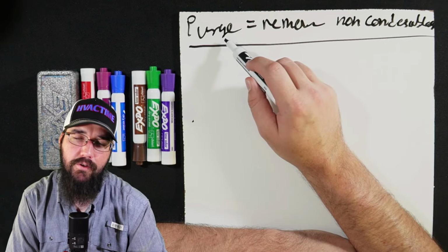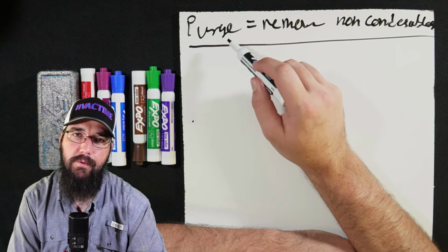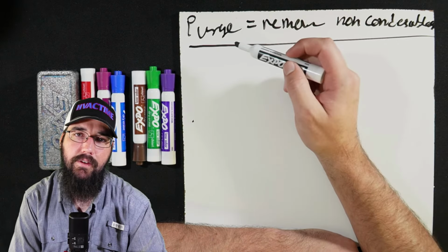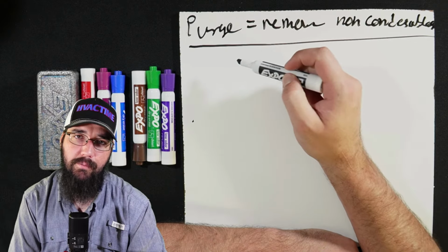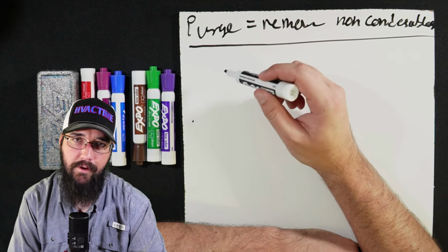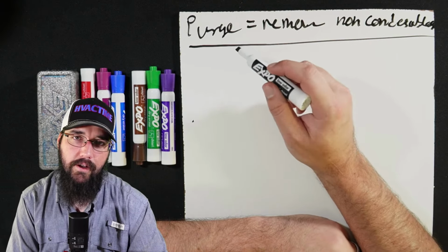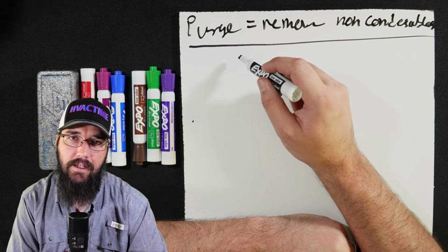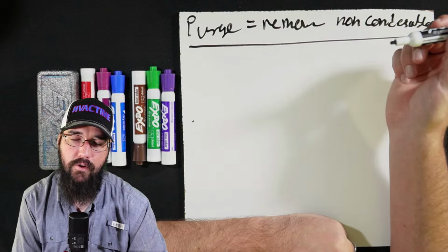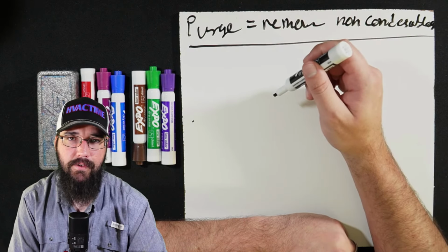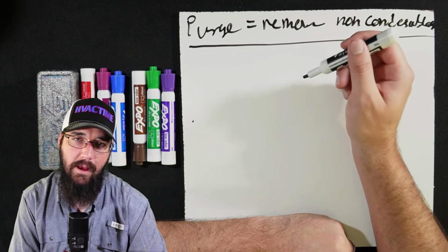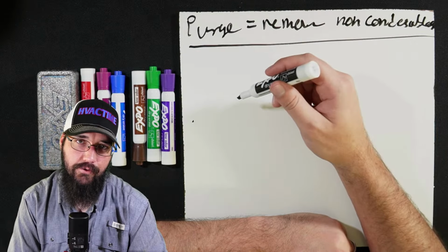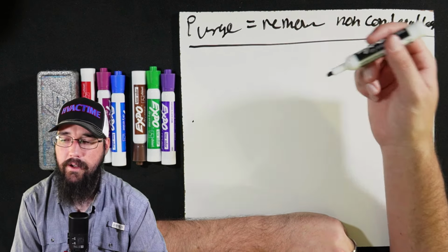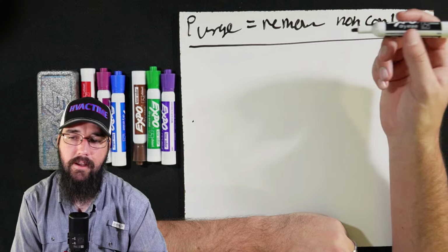To have a purge, we have a low pressure machine, which means that our chiller operates in a vacuum, especially on the evaporator side. That also means that if we have a leak on the chiller, we are drawing in atmosphere from outside. Now, what is atmosphere comprised of? Nitrogen, water, and some other stuff, right?